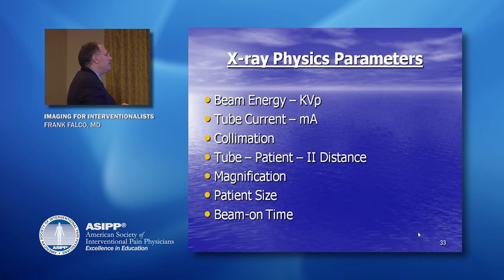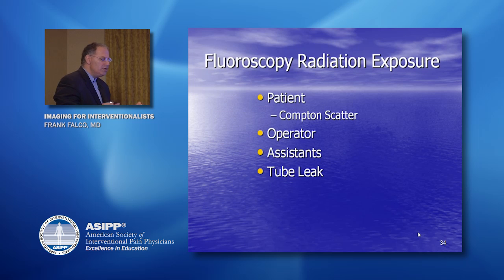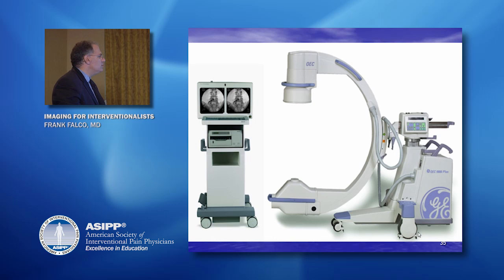Okay, X-ray physics parameters. We're looking at the beam energy, the kVp, the tube current, milliamps, collimation, tube to patient distance, the II distance, magnification, patient size, and beam on time. Fluoroscopic radiation exposure: patient, operator, assistants, and tube leak.